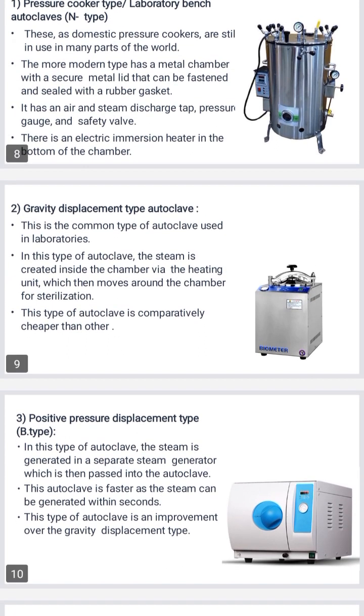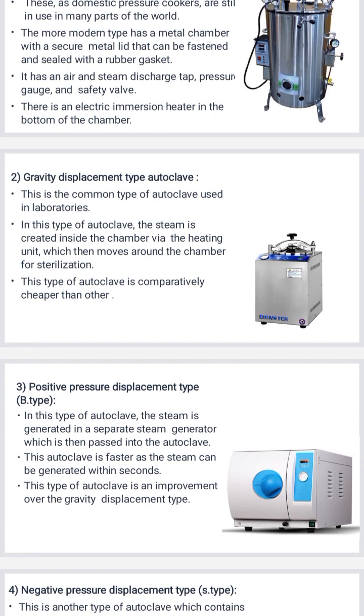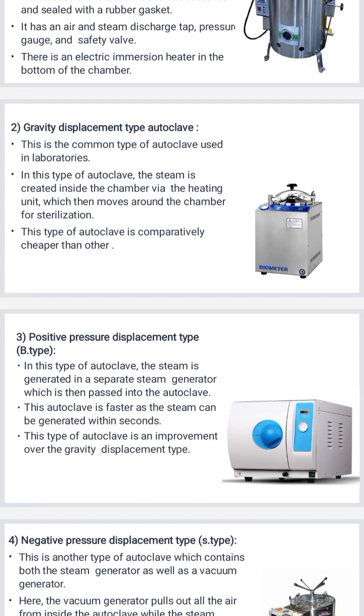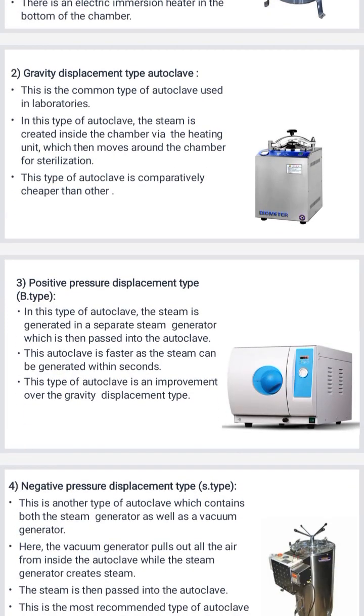Two, gravity displacement type autoclave. This is the common type of autoclave used in laboratory. In this type of autoclave, the steam is created inside the chamber by the heating unit, which then moves around the chamber for sterilization. Third, positive pressure displacement type, or B type. In this type of autoclave, the steam is generated in a separate steam generator, which is then passed into the autoclave. This autoclave is faster as the steam can be generated within a second. This type is an improvement over the gravity displacement type.